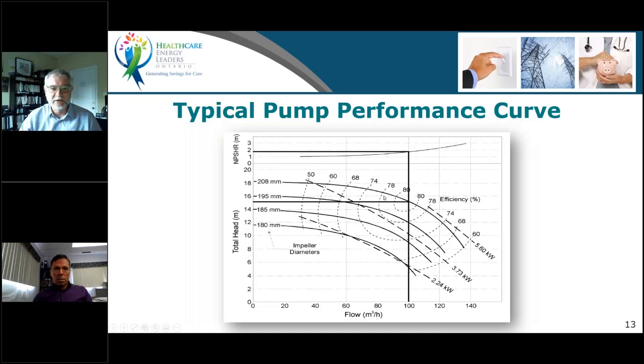So if we were concentrating on this one line here, we'll see that if we operate right in the middle of this little center, I call these egg-shaped curves, we're probably north of 80% efficiency on that pump. But as we move to higher heads, meaning higher pressures, as we throttle that pump, we're actually going to move. If we throttle that pump to 50% of flow, we've dropped from, say, 82% to probably 65% or 63% efficiency. That's a dramatic drop for just closing a valve.